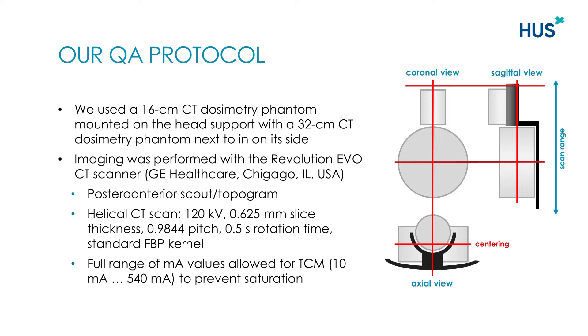We use the head and the body CT dosimeter phantoms in the scan. The head phantom was mounted on the head support of the patient table and the body phantom was placed next to the head phantom on its side. The phantoms were centered as shown in the figure here.